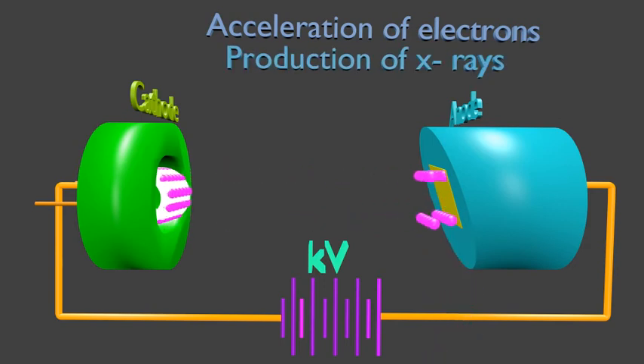These electrons start their journey from cathode side with a velocity zero and attain very high speed on reaching anode side of X-ray tube. If we have applied 70 KV at the X-ray console, the electron at reaching anode side will have a kinetic energy of 70 KEV. So the kinetic energy of electrons will increase from zero to KV range while traveling across X-ray tube.